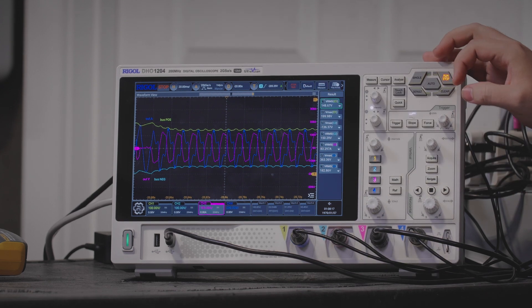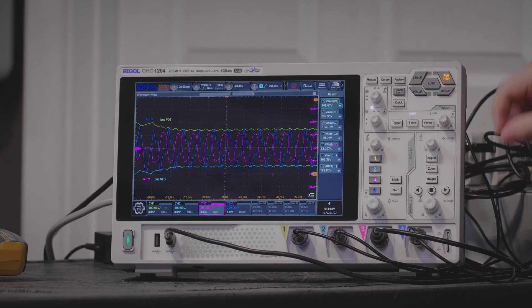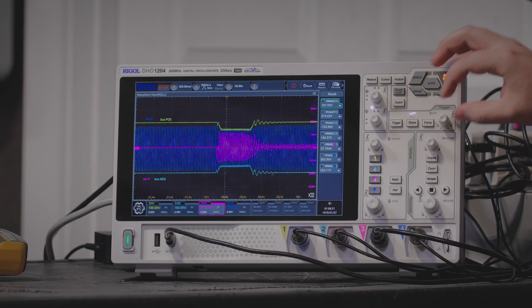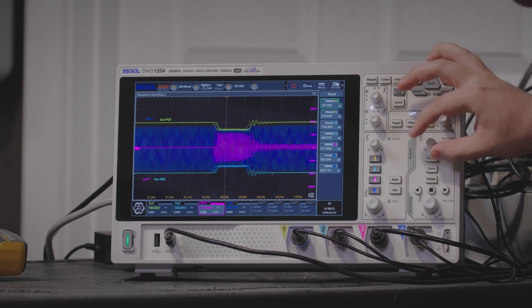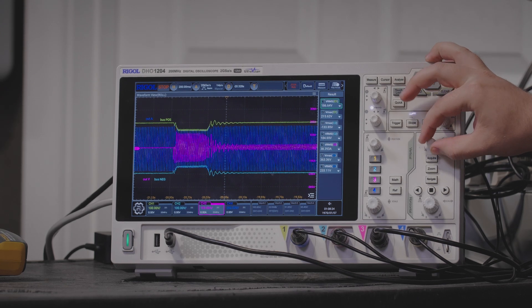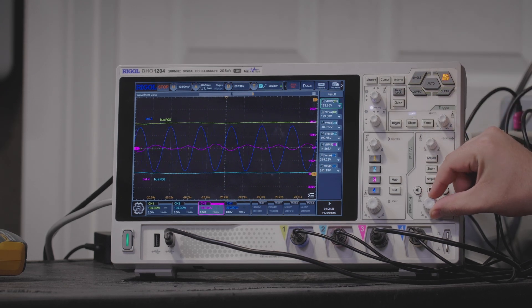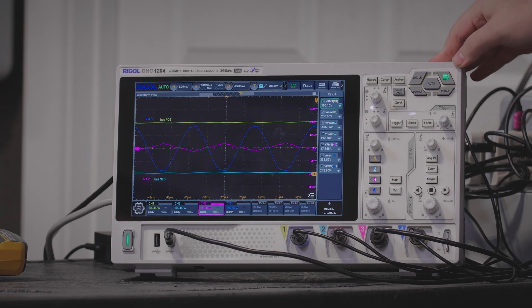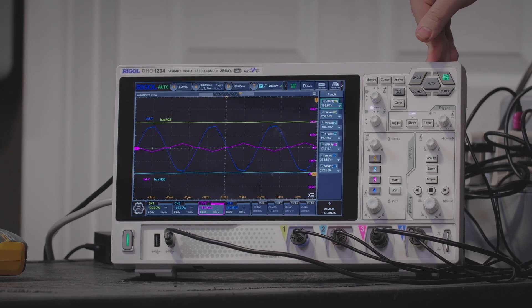You can see the high bus dips down for a little bit during the inrush, but then it completely smooths out as it stabilizes. And that's what it looks like with just the five-ton running.